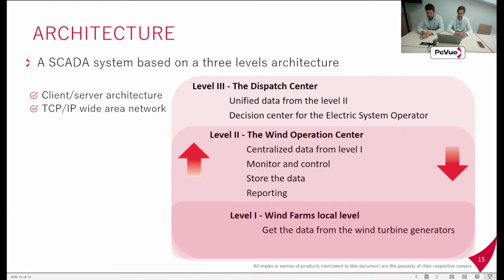This is based on the classical client-server architecture over TCP/IP wide area network, but it also works with fiber and satellite. So 3 levels. The first one is the local asset, with a SCADA system to monitor and control this asset, acquiring data from the field. This level 1 will communicate with level 2 - not all the data, but it has the capacity to serve the amount of data through what we call front-end servers, level 2.